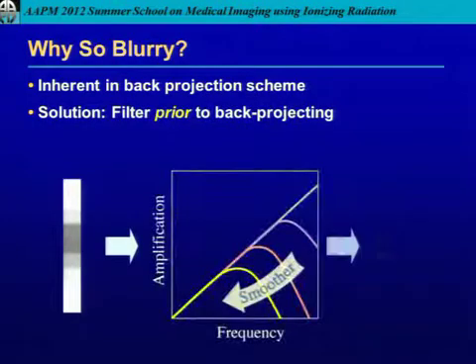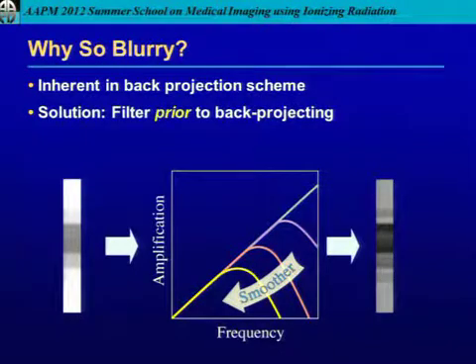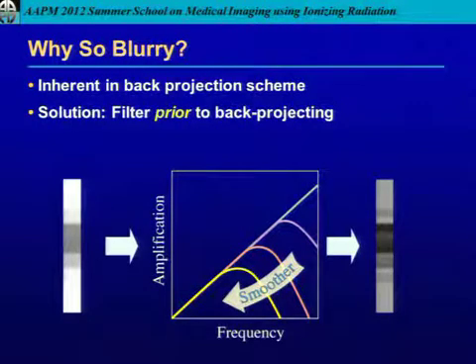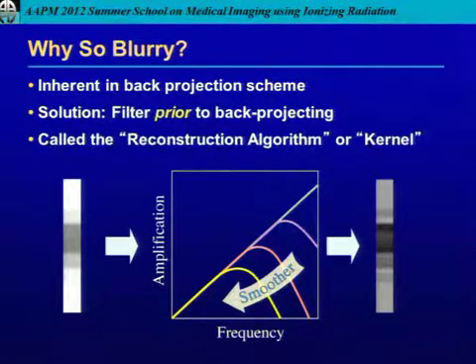There is something we can do about the blurriness: we can filter the data. That data isn't really a grayscale — it's just numbers and signals. We can selectively amplify the higher frequencies and sharpen it. So in a sense, what we're doing is undoing the blurriness before the blurriness exists — this filtering is done prior to back projecting, not like a Photoshop filter applied to the final image. This is called the reconstruction algorithm, or the kernel.